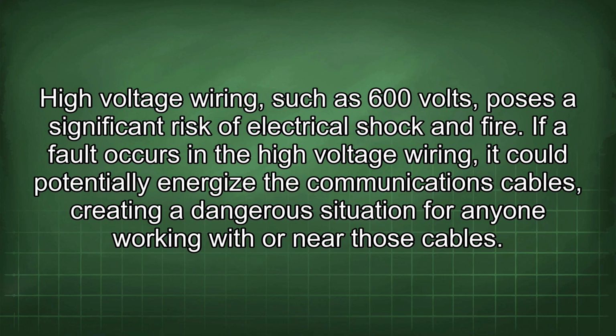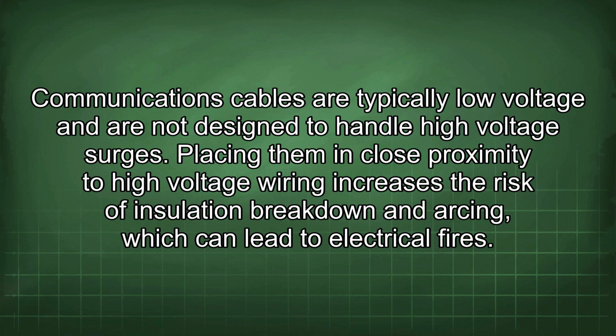High voltage wiring, such as 600 volts, poses a significant risk of electrical shock and fire. If a fault occurs in the high voltage wiring, it could potentially energize the communications cables, creating a dangerous situation for anyone working with or near those cables. Communications cables are typically low voltage and are not designed to handle high voltage surges.